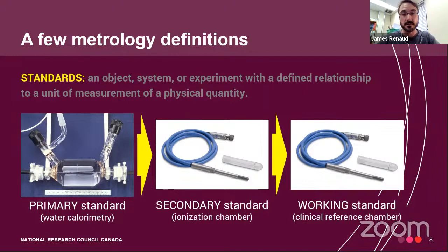I'm going to use absorbed dose in this case as an example. Standards are the fundamental reference for a system of weights and measures against which all other measuring devices are compared. And there's a hierarchy to standards. In fact, it's a 3-level hierarchy. At the top, you have the primary standard. In the case of absorbed dose, at least in this country, the primary standard is based on water calorimetry. All primary standards are made to the highest metrological quality, and they are the definitive definition or realization of their unit of measure. It's sufficiently accurate so that it does not need to be calibrated. It's not subordinate to any other standard of the unit in question.